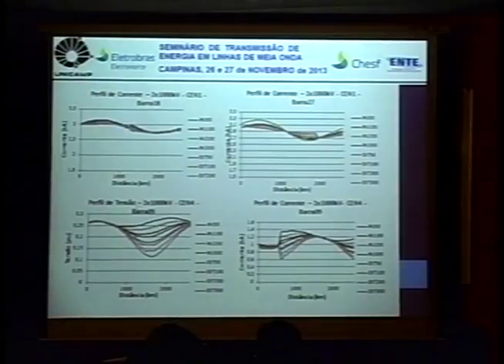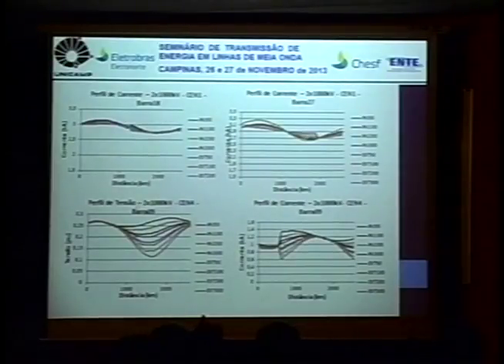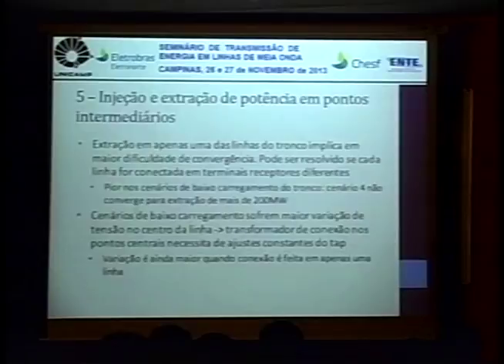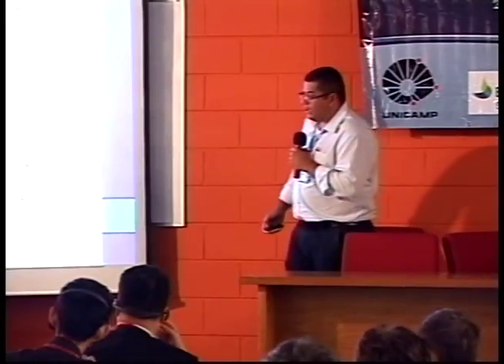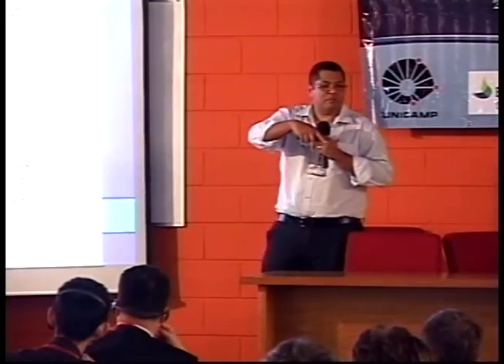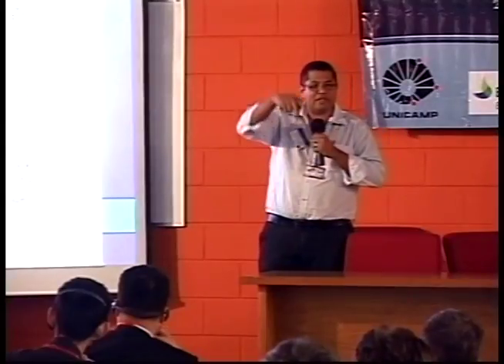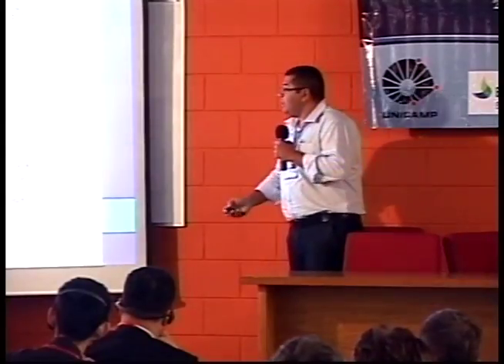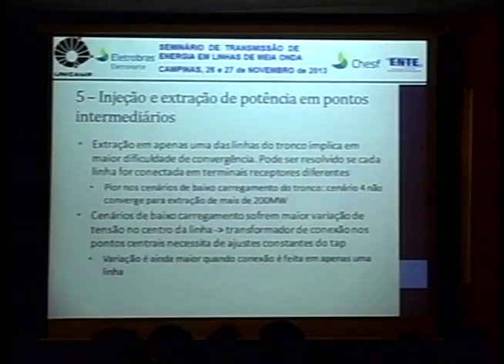For many cases, we could not get any convergence with extraction above 300 megawatts. For example, this case only goes up to 200. We cannot go up to 300 because there were problems with the load flow in the network. And in those cases, we're removing from the three lines at the same time, the same amount from each of them.